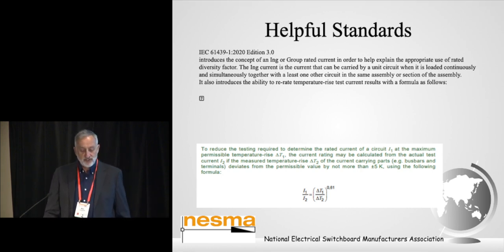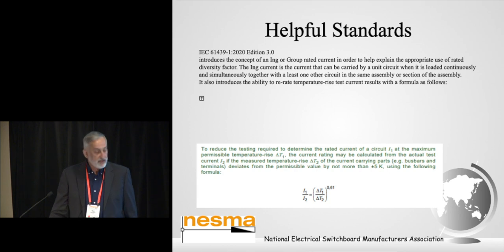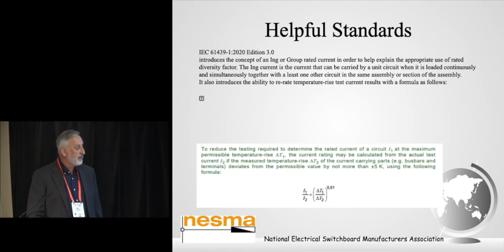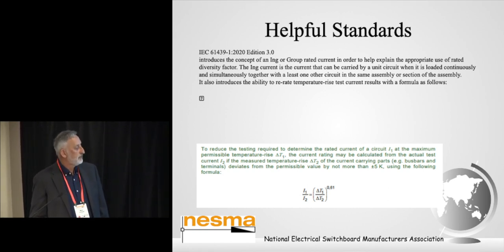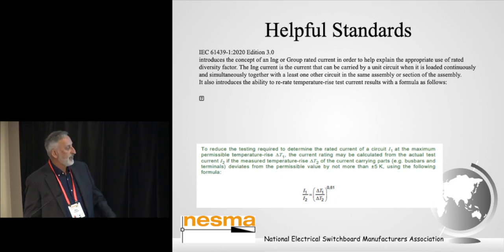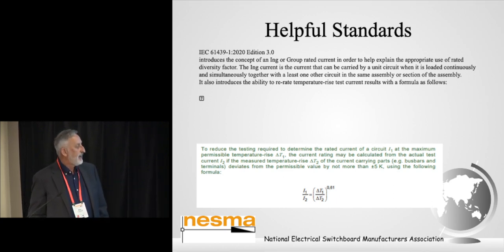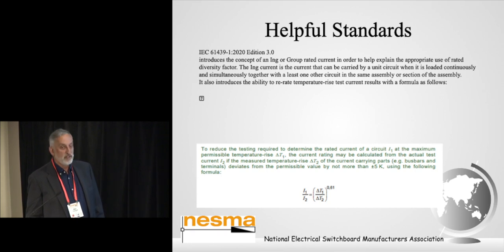It also introduces a very useful formula that we used at the station for many years. To reduce testing required to determine the rated current of a circuit, the maximum permissible temperature rise, that current may be calculated from the actual test current. And so what it does, the standard limits it to plus or minus 5 degrees, but it does give you an indication, if you go above that, of the performance of a unit at a nominated current compared to a tested current.